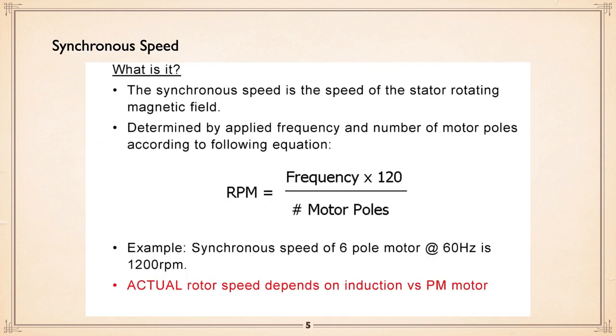Now, synchronous speed is the speed of the stator rotating magnetic field. Frequency and number of poles go into this equation: 60 hertz in our case, so 7,200 on the top divided by the number of poles. For example, a 6-pole motor, 7,200 divided by 6 would give you 1,200 RPM.